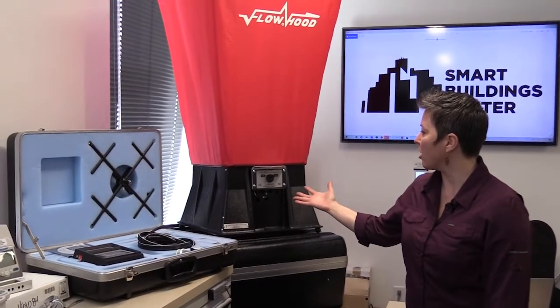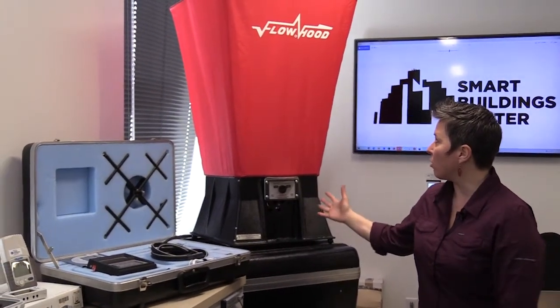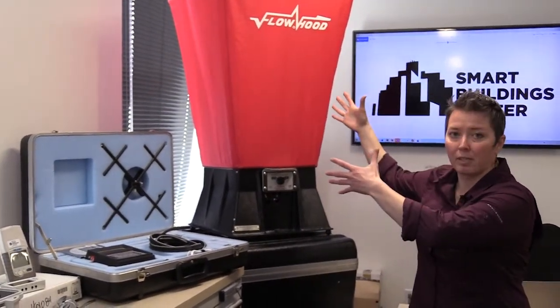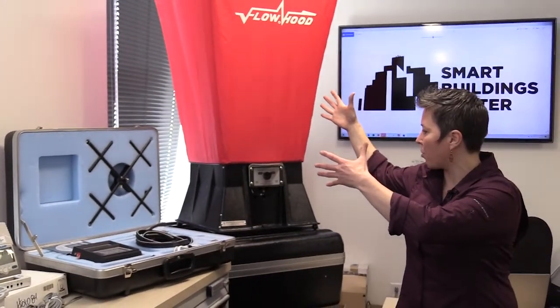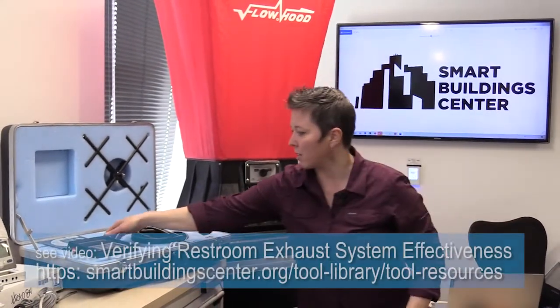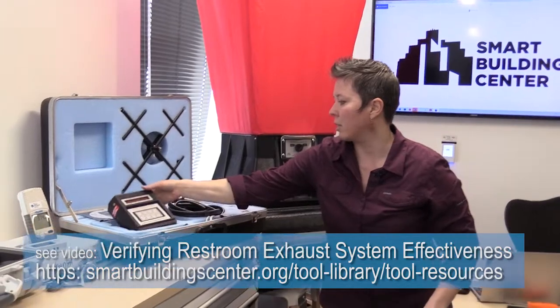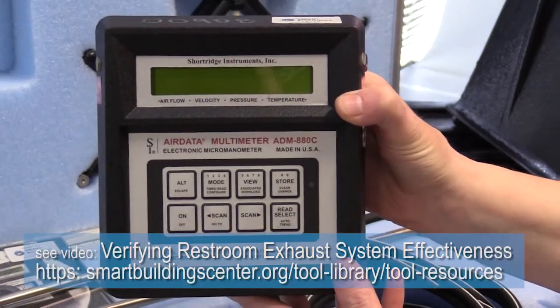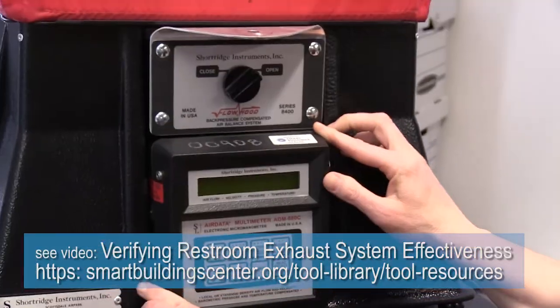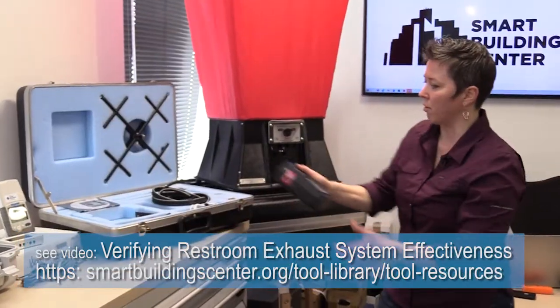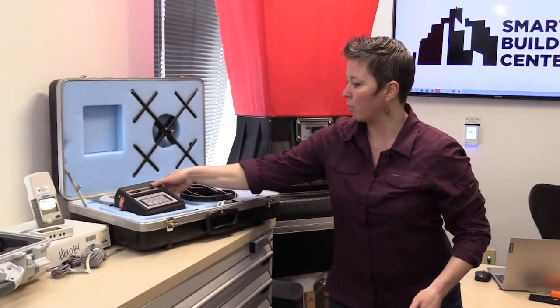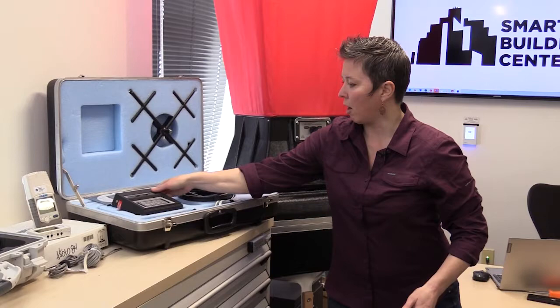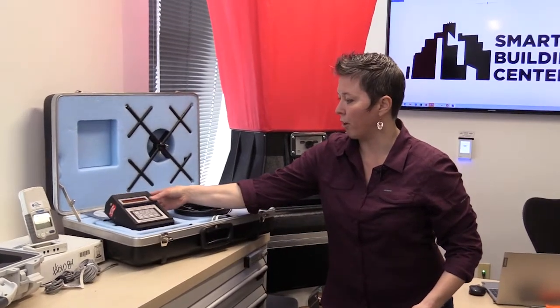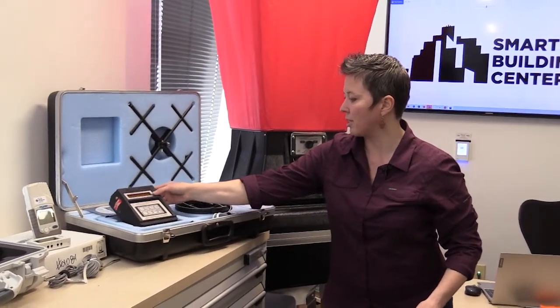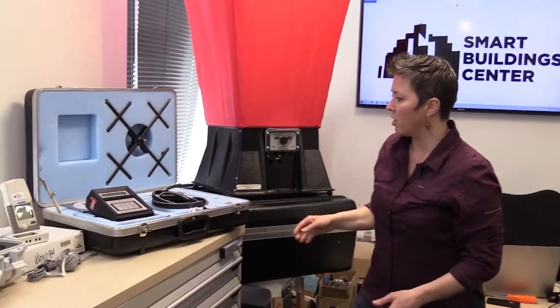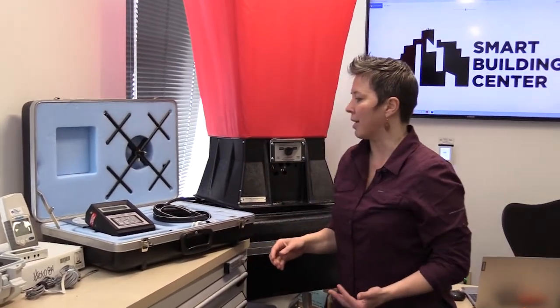This one is a Shortridge flow hood, so you hold this up tight up against the grill if it's on the ceiling, for example, and this has a meter that can plug into the flow hood or be used as a standalone. So it just plugs in here and it will measure the flow coming out of that grill. Now, this meter is also very versatile. As I mentioned, it can be used standalone for other applications, so measuring pressure and velocity.